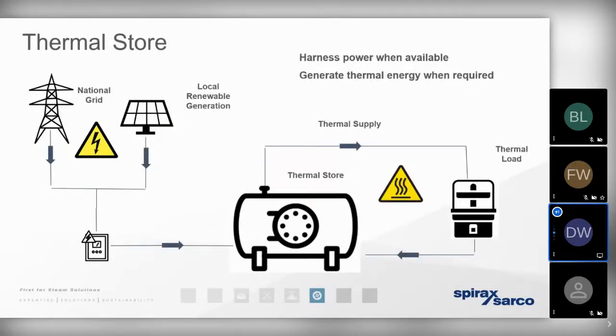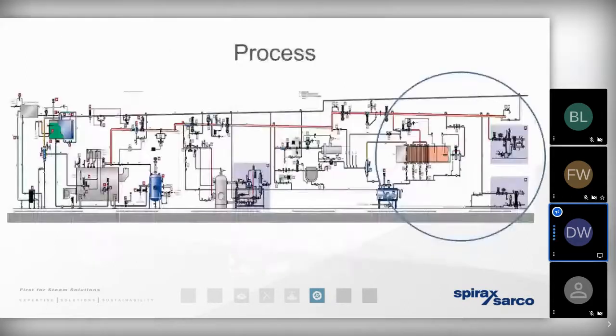So this would work very, very well if we've got a process that's got a sudden requirement for a relatively large mass of steam in a very short period of time. It can supplement a steam using process, but it wouldn't necessarily replace a traditional steam boiler that's utilizing an alternative source of fuel altogether. Moving forwards, we need to give thought to how we're utilizing the steam. We need to give thought to how we're using that energy at the process, possibly even look at how we can reduce the demand. And if we move forwards, we can look at different ways where we can use maybe even waste heat more efficiently.